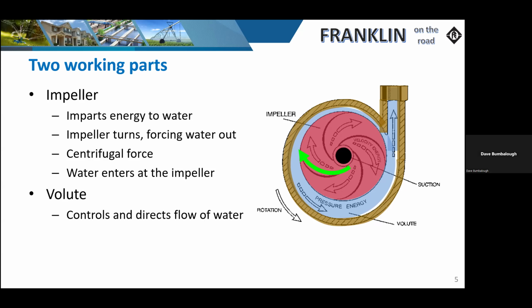So when we're looking at basically the pump itself, as the impeller is spinning, we refer to that as velocity energy. So in the eye of the impeller, which is an essential portion here, a water molecule will be basically grabbed by the impeller through natural gravitational force. When it is in the eye of the impeller, as it is spinning, it will eventually make its way out to the outside edge. So we're allowing that velocity energy to give us the pressure energy to be able to move that volume of water plus build pressure in that system.